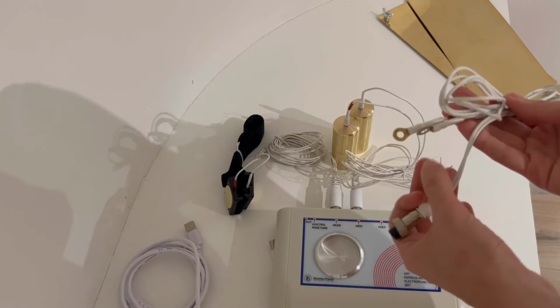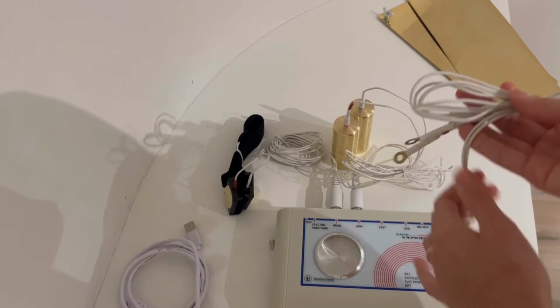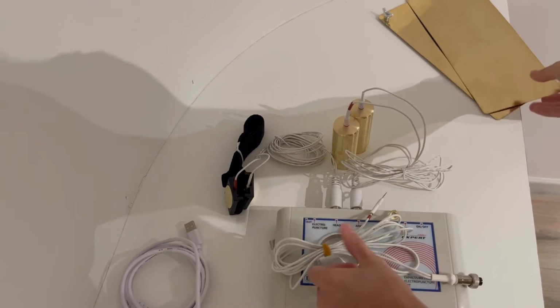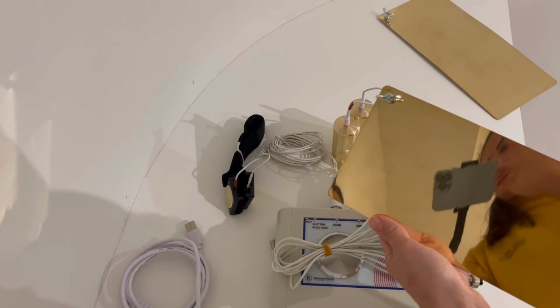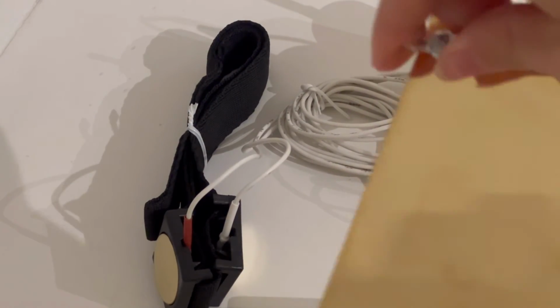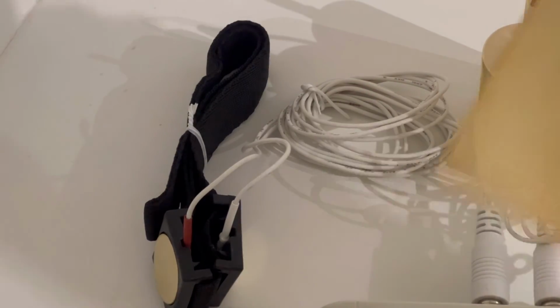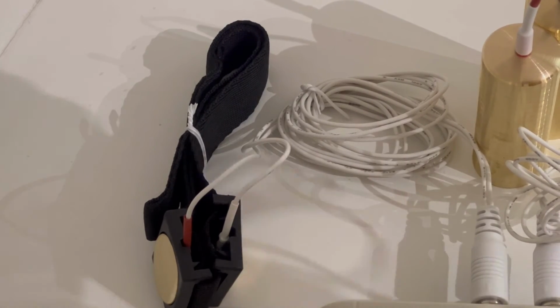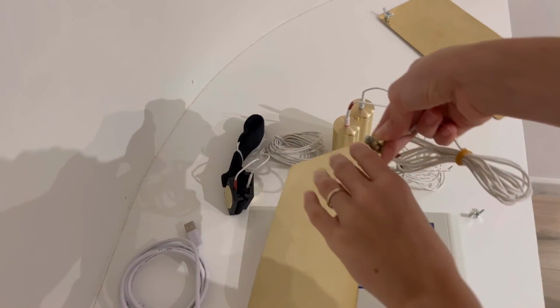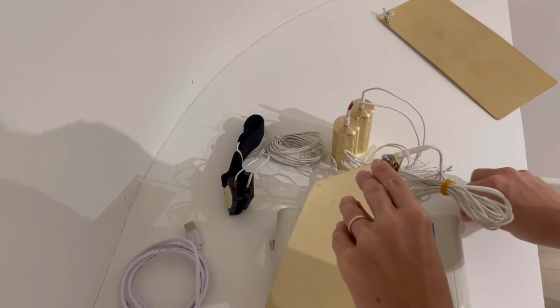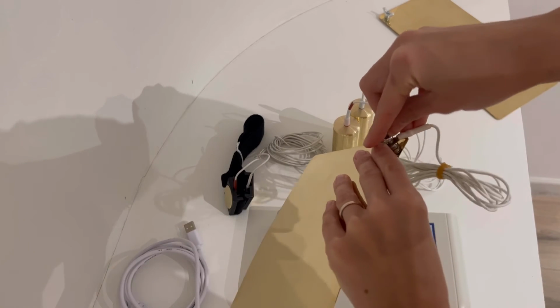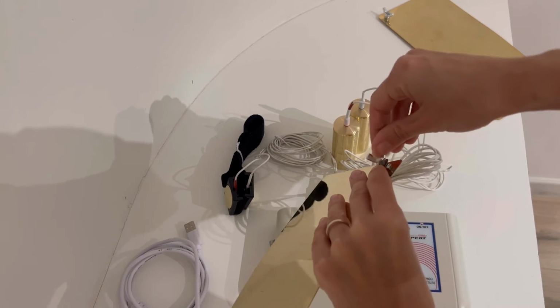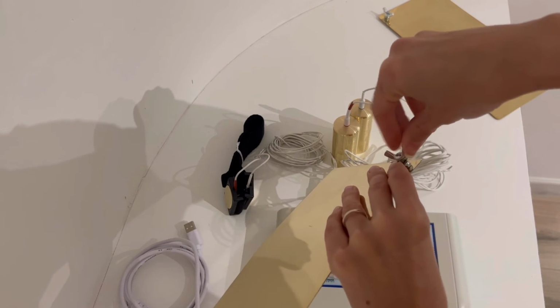Here are feet electrodes with its specific cables, and here you can find the feet plates themselves. First, we need to unwind the bolt, like I'm showing on the video, and we connect the cables. For the feet electrodes, you can already choose left and right side, and when you will be doing it on practice, I recommend you to place the electrodes on the floor and to tighten the bolts there. It will be much easier, much more comfortable than doing it away, as I'm showing on the video.